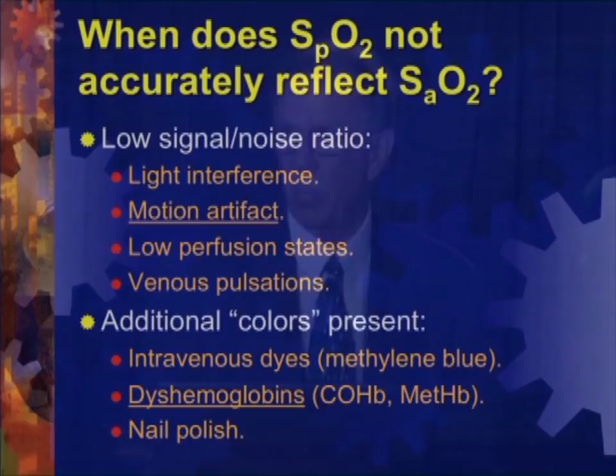Motion artifact we'll talk about in a little bit more detail, but you can imagine if I'm wiggling my finger, what's happening? The arterial blood is not the only thing that's pulsating now, right? Everything is pulsating. Aoyagi's assumption. Low perfusion states, shock, for example, and venous pulsations. I tell my residents, do this, not after a full meal. Put a pulse oximeter probe on your ear, measure your saturation standing up, go over to the corner and stand on your head, put your feet against the wall and stand upside down and see what the pulse oximeter says. Almost all conventional pulse oximeters will read a number 4 to 8 points lower when you're standing on your head, and the reason is the venous blood is pulsating, venous pulsations.